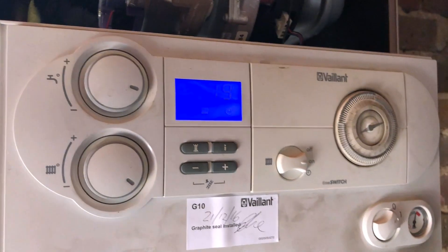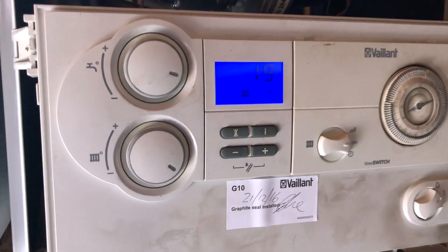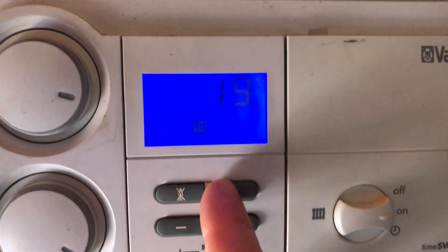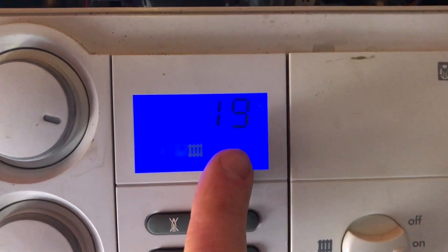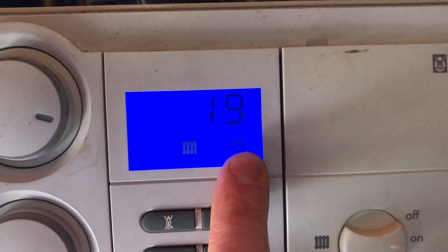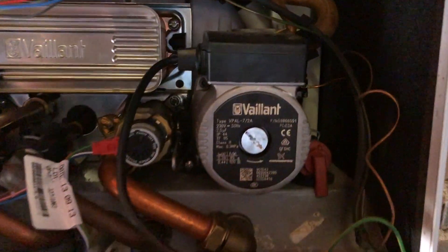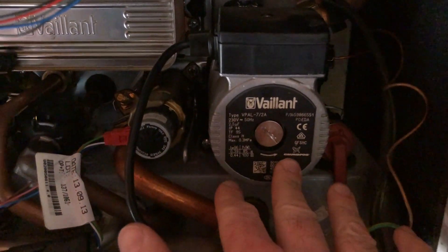We've got a boiler that's going to show up an F75 code in a minute. This is a Vaillant Ecotec Plus 837 and I know we're going to get an F75 because the boiler tries to run the pump as this little symbol comes up. That means the pump's trying to run. I can't hear any pump kicking in — this is our pump and the pump isn't running at all.